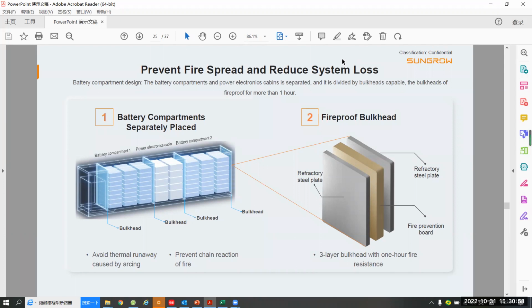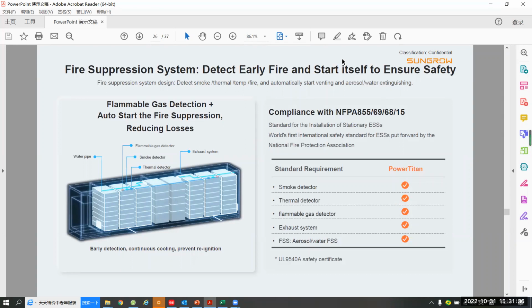From the picture, we can see that the bulkhead has 3 layers, and 2 layers are refractory steel plates, and 1 layer is the fire prevention board. It can fireproof for more than 1 hour. The whole structure design of the ESS container can avoid the thermal runaway caused by arcing. Also, it can prevent the chain reaction of fire to make the ESS container safer. And another safety system protection is the fire suppression system. It's designed in 3 levels. The first level is the flammable gas detection in early fire. It includes the smoke detector, thermal detector, and flammable gas detector.